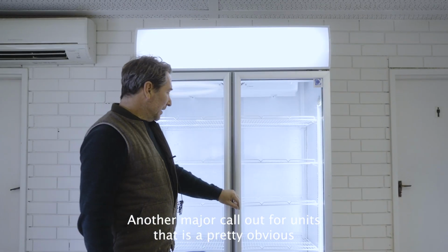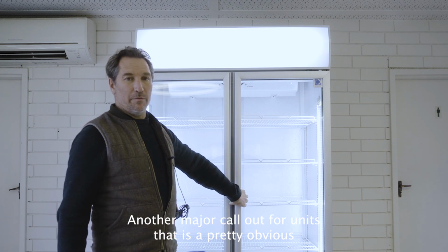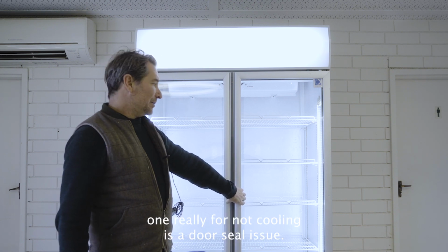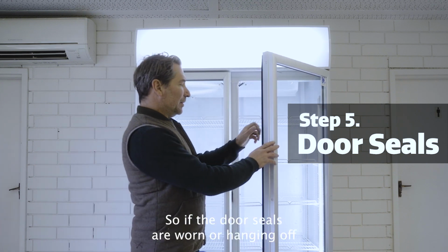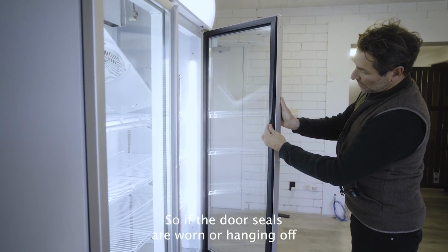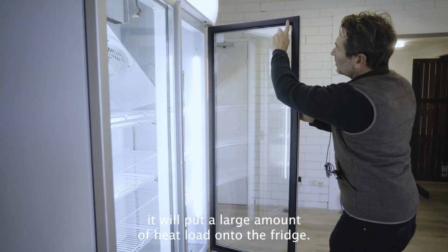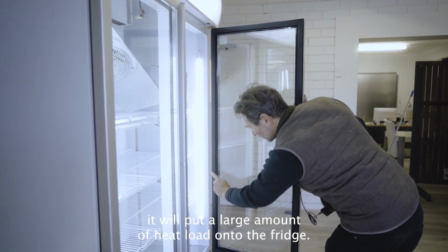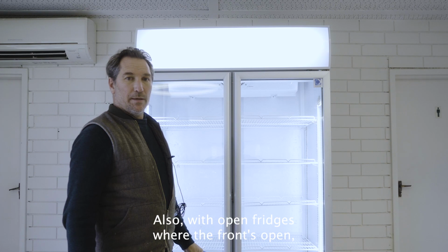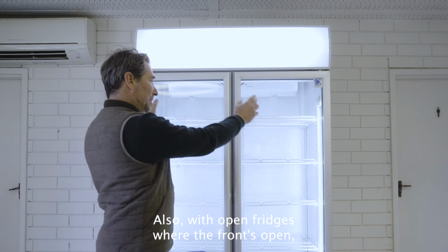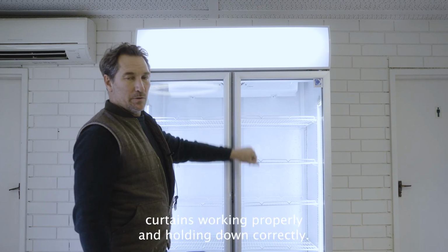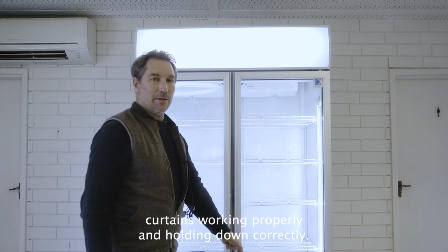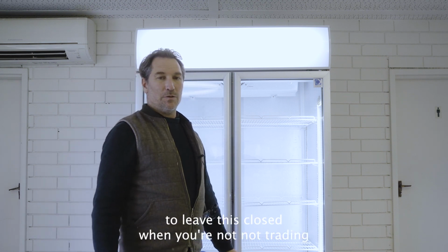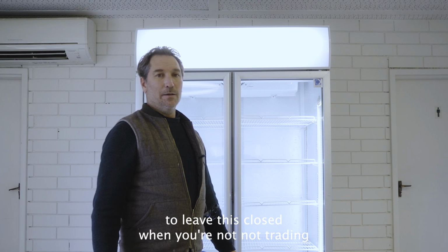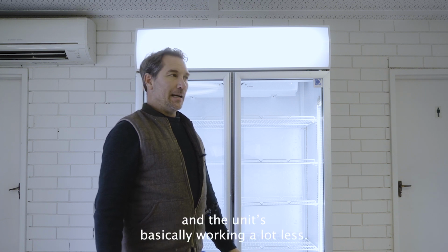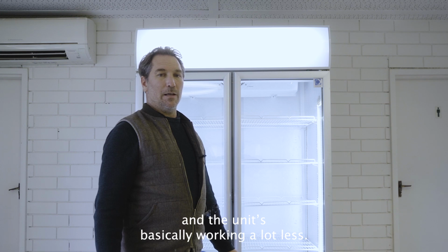Another major call out for units not cooling, a pretty obvious one really, is a door seal issue. So if the door seals are worn or hanging off and there's air entering the unit, it'll put a large amount of heat load onto the fridge. Also with open fridges, where the front's open, you want to check your night curtains are working properly and holding down correctly. Again, it's really important to leave this closed when you're not trading, because it'll save a lot of power and the unit's basically working a lot less.